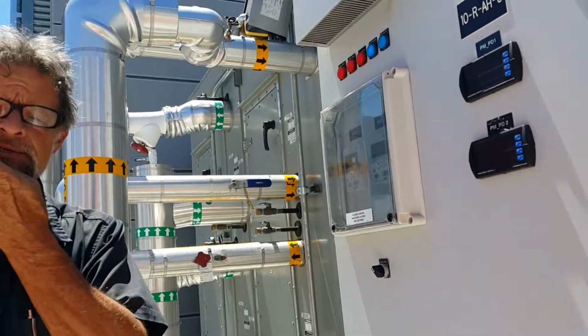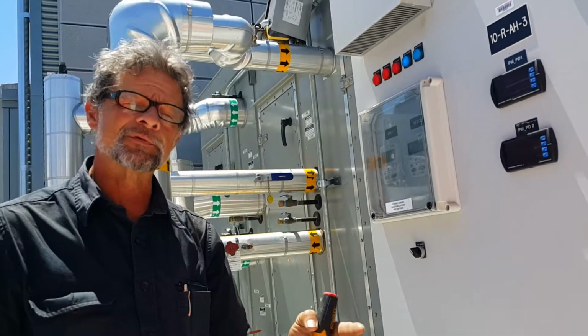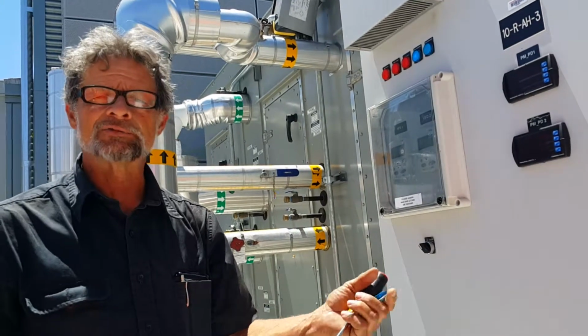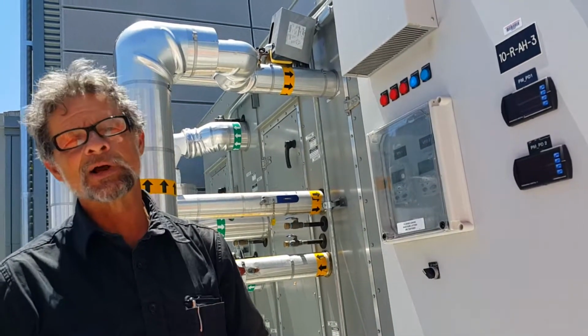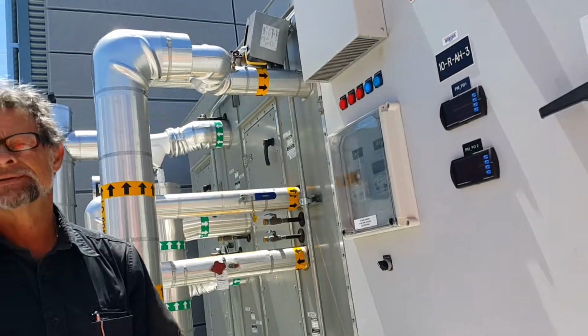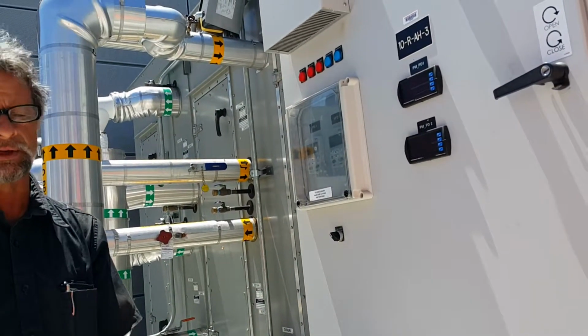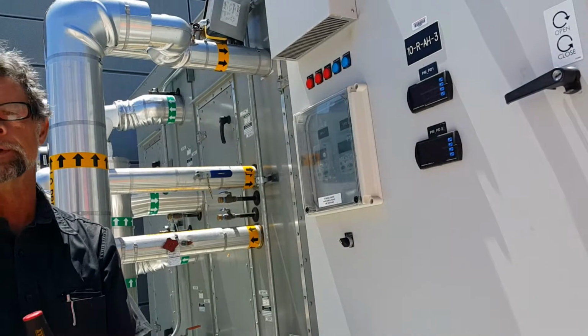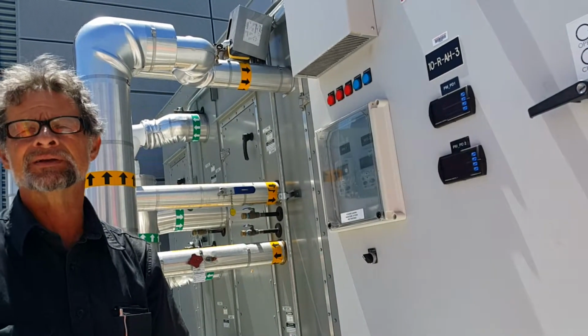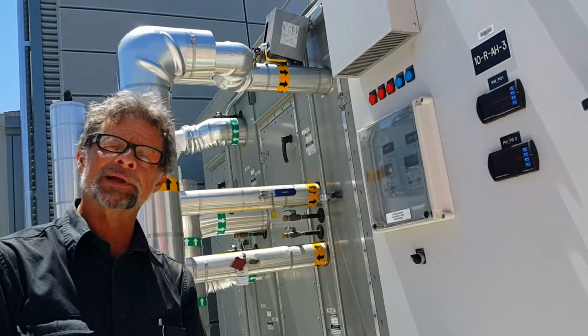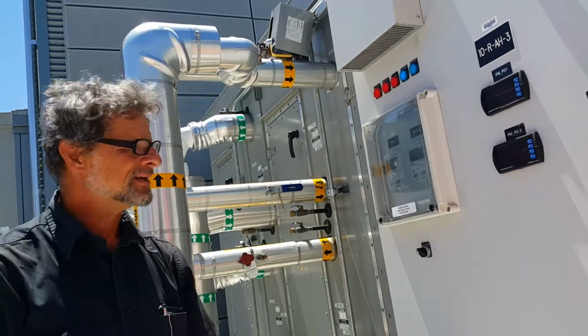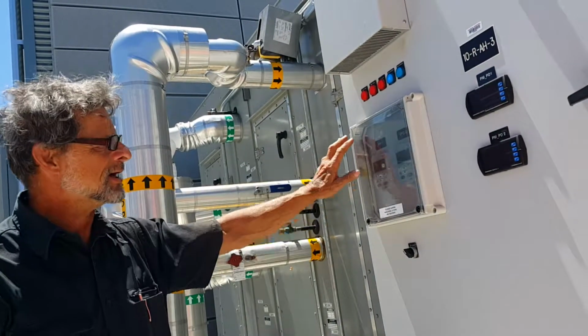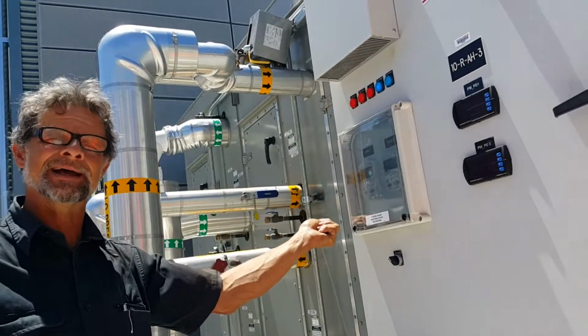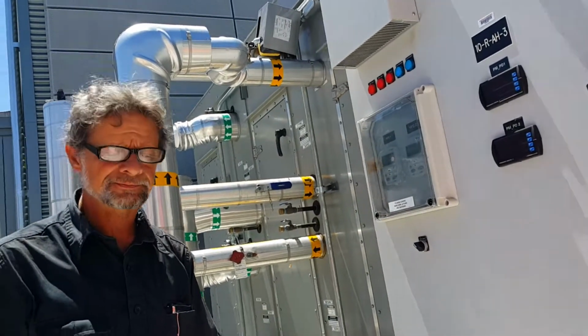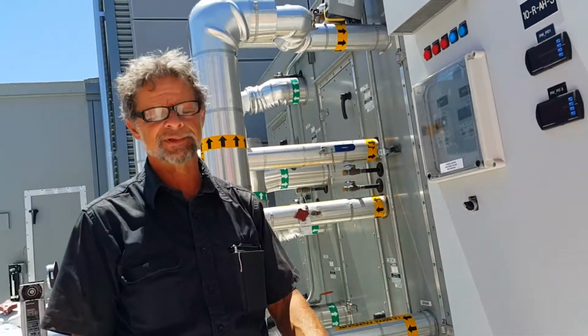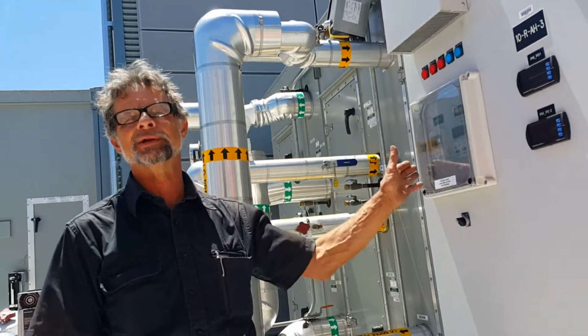The problem with drives is, even on that relay, in order for that relay to work, the drive's got to work. So if the drive is fairly intact and it blows up, say, an input rectifier or an output transistor, and there's still enough of it in place on the control side that says, well, I have a problem, I'm going to shut down, I'm going to go into alarm and switch my contacts, then the other one will come up and run. If it just plain blows up, it's down. They can't do anything about it.